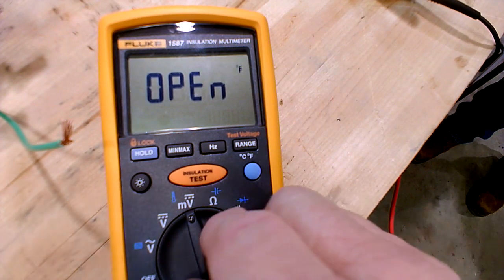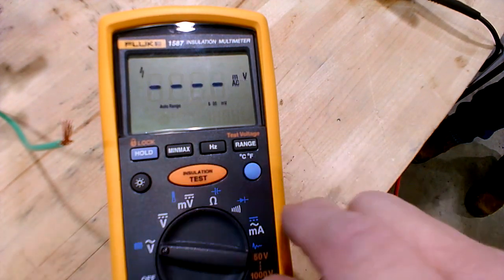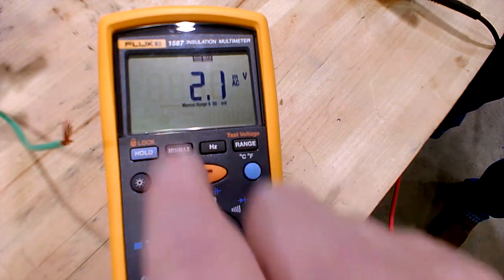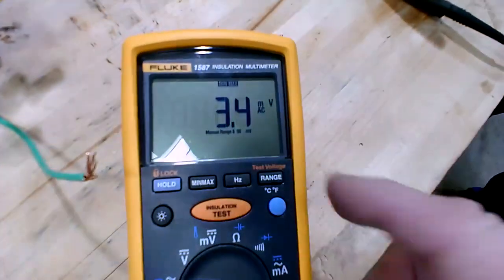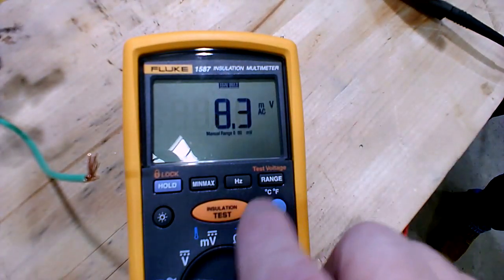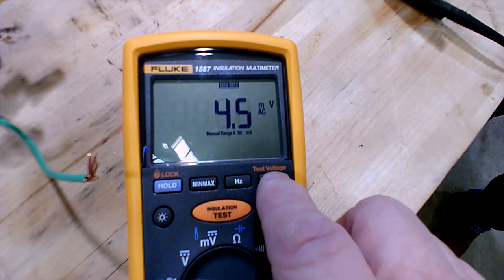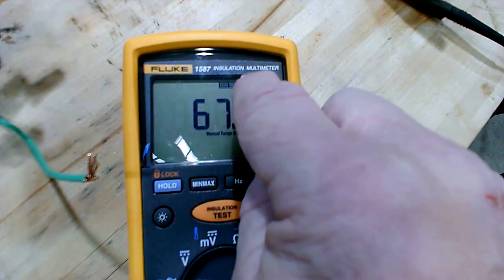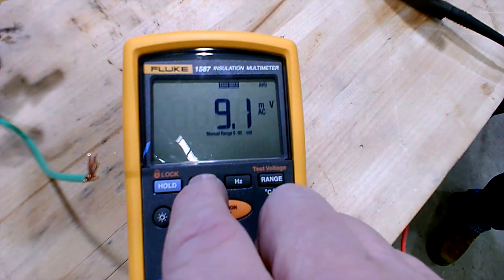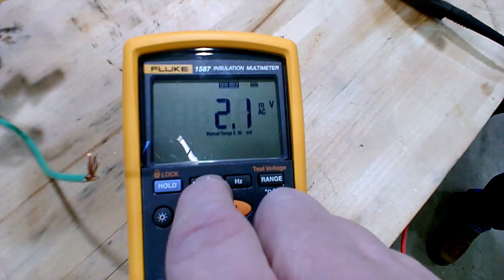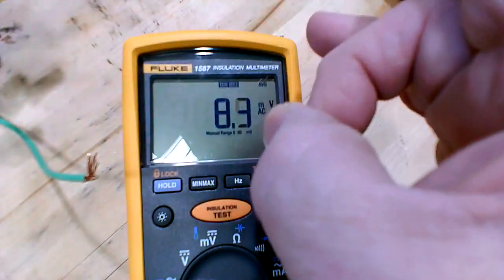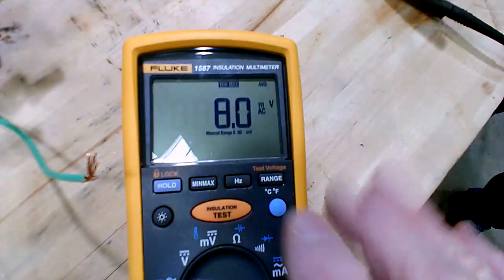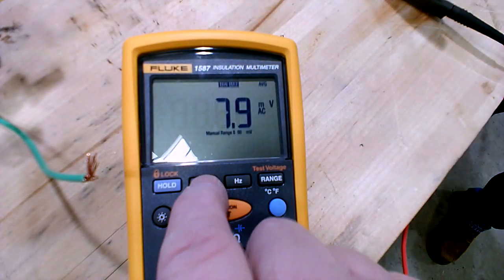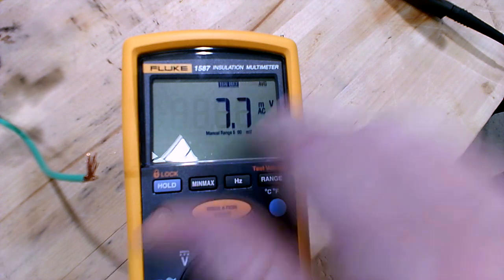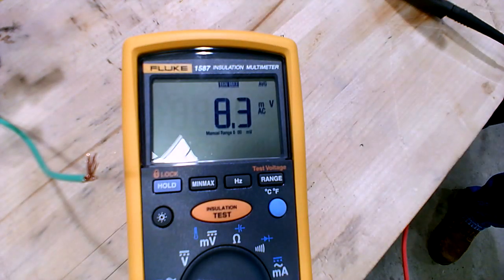If you're doing voltage and you want a minimum maximum reading, you hit that, and over time it'll store the lowest and highest readings. It'll toggle: min, max, average, max, min, average. So if you want to check amps on something over a long period, you put your amp clamp in, put it in that mode, and it's going to store the average, the max, and the min over a long period of time.